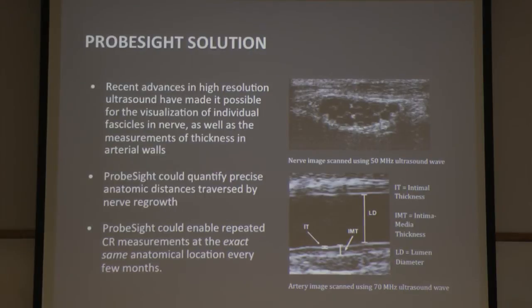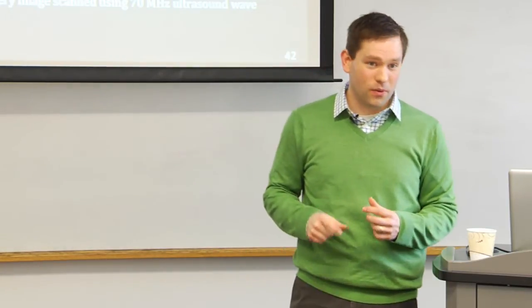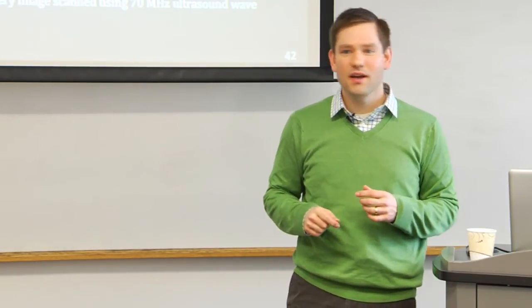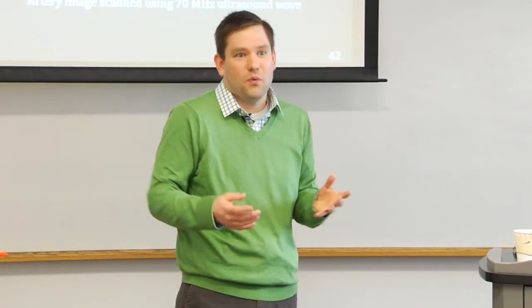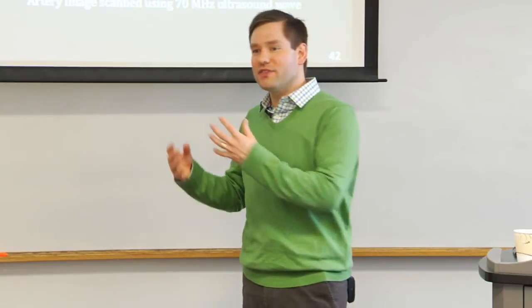And this is problematic because while we could take the scanner, this brand new system, and put it on you and get a measurement of intimal wall thickness, if we come back 3 months from now and get a new measurement, even a subtle shift in the angle of the probe will have us imaging a sufficiently different patch that we can't say whether any differences we measure are because we just imaged a different place in the vessel and it was bigger, but so what? Maybe it was already bigger there. Or is this actually a meaningful change that's happened over time?